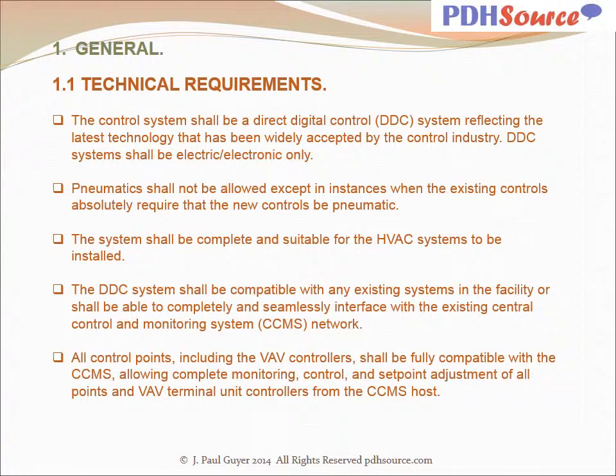The control system shall be a direct digital control (DDC) system reflecting the latest technology that has been widely accepted by the control industry. DDC systems shall be electronic only. Pneumatics shall not be allowed except in instances when the existing controls absolutely require that the new controls be pneumatic. The system shall be complete and suitable for the HVAC systems to be installed. The DDC system shall be compatible with any existing systems in the facility or shall be able to completely and seamlessly interface with the existing Central Control and Monitoring System (CCMS) network. All control points, including the VAV controllers, shall be fully compatible with the CCMS, allowing complete monitoring, control, and set point adjustment of all points and VAV terminal unit controllers from the CCMS host.